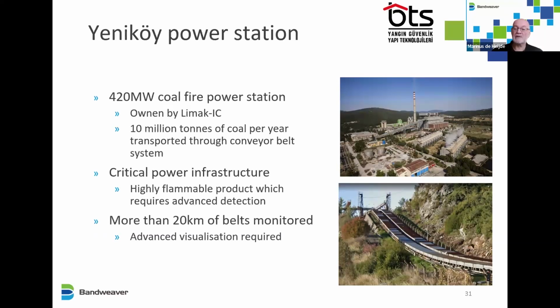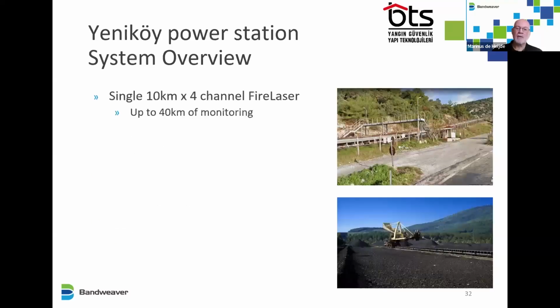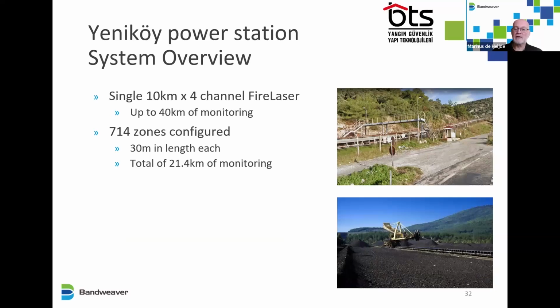At this power plant, we had 20 kilometers of belts monitored, which also required advanced visualization, so people could go to the right location. Because if you've got 20 kilometers, it's necessary to have advanced visualization. So we used one single unit, a 10-kilometer unit with 4 channels, so it could monitor up to 40 kilometers of cable. But we split it up into 714 zones, which were all 30 meters in length. So the total monitoring we did there actually was 21.4 kilometers.